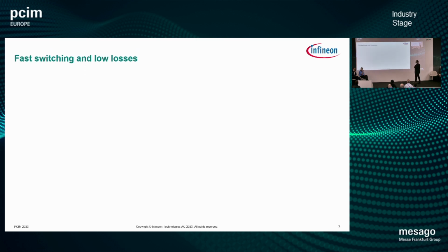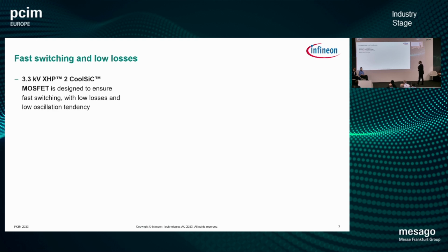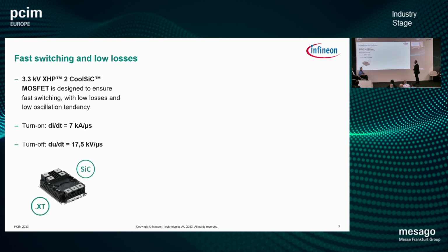Next, I would like to focus on the combination. What does this combination of a low inductive design and fast chips bring? The 3.3 kV MOSFET, which we are introducing at PCIM this year, is designed for very fast switching and low losses. We are talking here about a turn-on speed of around 7 kiloamperes per microsecond, and a turn-off speed of almost 17.5 kV per microsecond.